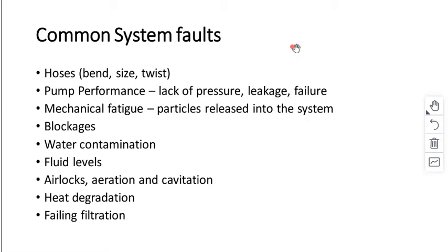We've got maybe leakage inside the pump, possibly failure. So this can be a fault and cause other faults. Mechanical fatigue, particles released into the system. Okay, that's one big problem. Blockages, water contamination. That doesn't mean that the water is contaminated, but the water contaminates the hydraulic fluid. So that's an issue as well.